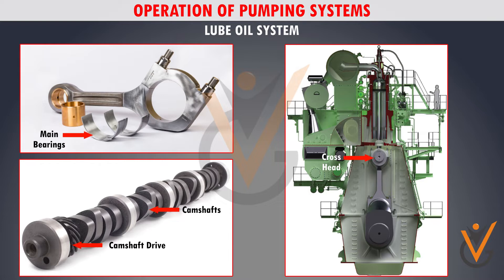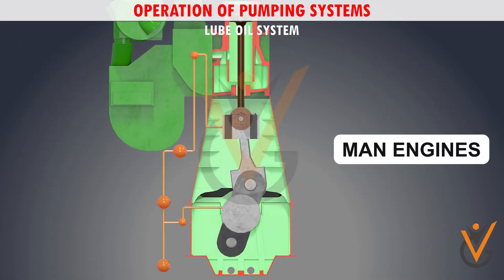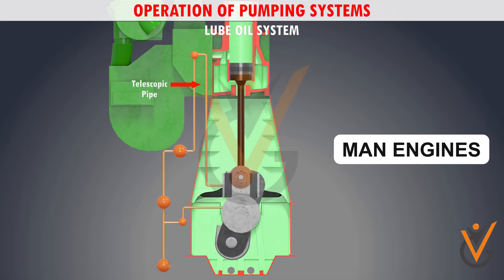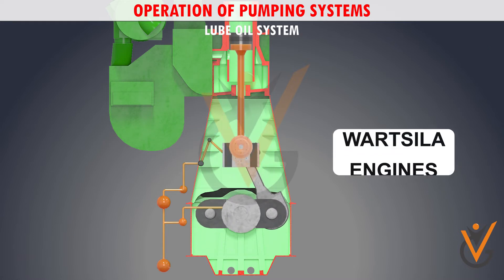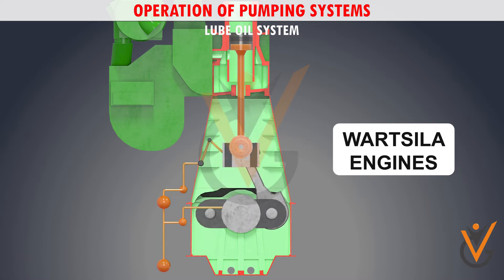A branch of lube oil goes to the crosshead. In MAN engines, the lube oil line is connected to the inlet in the crosshead using a telescopic pipe — it moves up and down along with the crosshead and oil is supplied from the top. In Wartsila engines, an articulated or swinging arm is attached to the crosshead, which supplies the inlet oil.